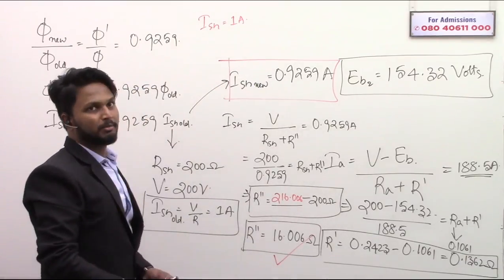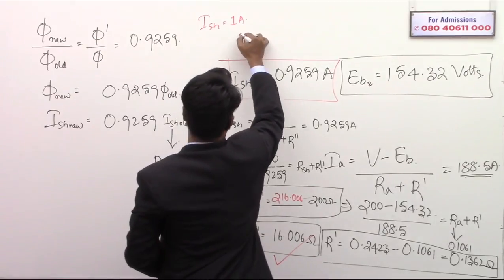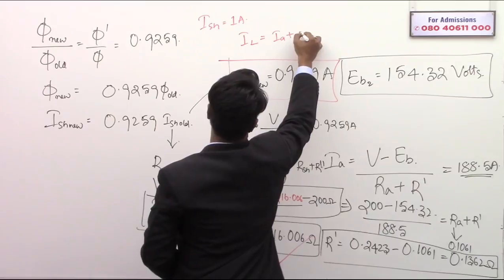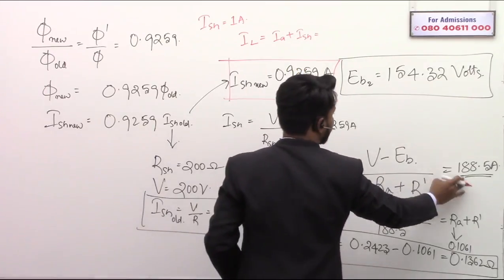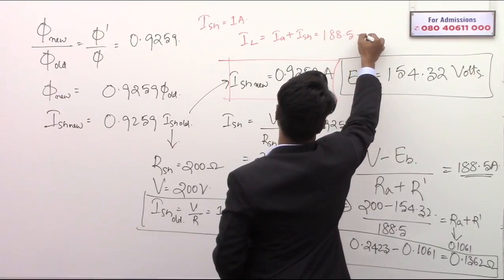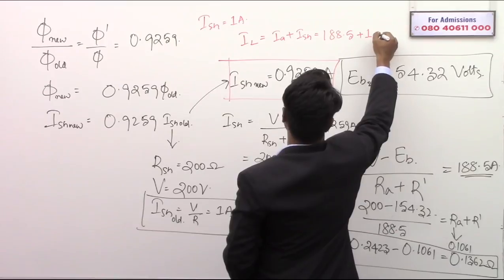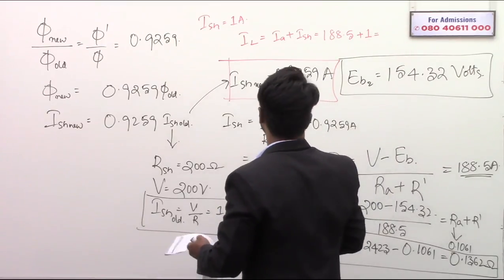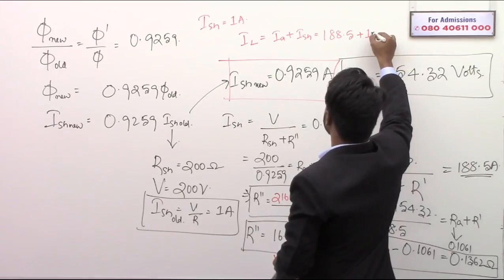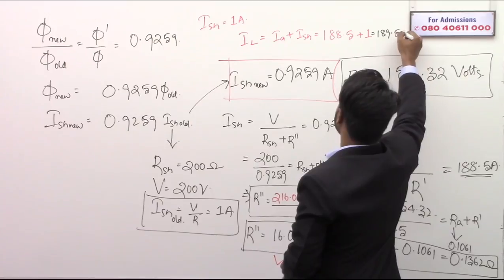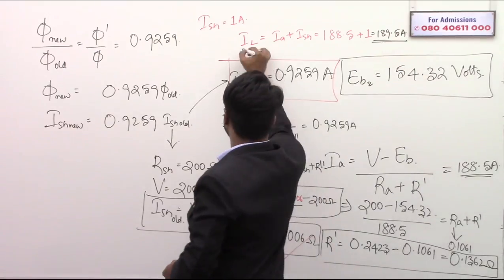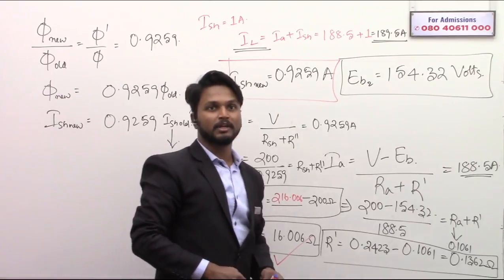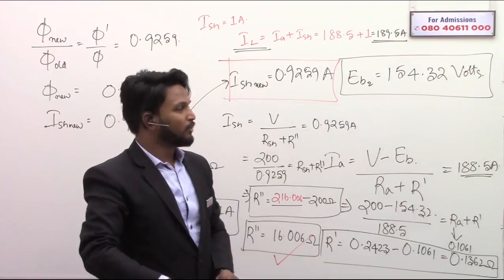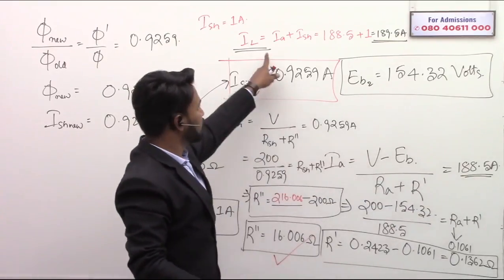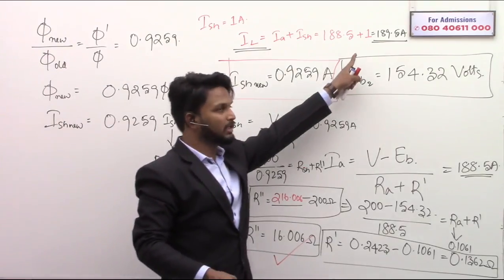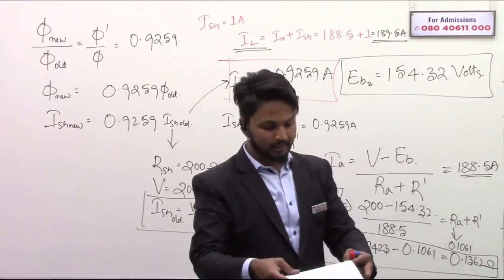There is a danger that you might commit a mistake here. What is the mistake? Line current IL is equal to IA, armature current plus shunt field current. How much is the armature current? That is 188.5 amperes plus 1 ampere, so the result should be equal to 189.5 amperes. As soon as you get the armature current, if you do not read the question properly, you'll end up putting 188.5 instead of 189.5. The correct answer is 189.5 for the third question.